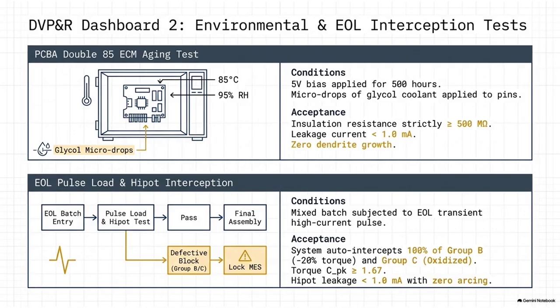They are deliberately attempting to force the electricity to break through the internal insulation, jump across the engineered creepage gaps, overwhelm the microfuses, and arc violently to the grounded metal chassis of the vehicle. What does the pack have to do to pass? The total leakage current escaping to the chassis must remain strictly under 1.0 milliamp.